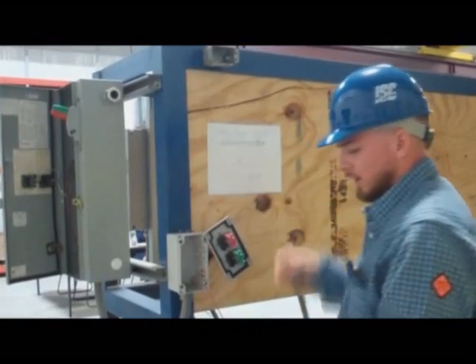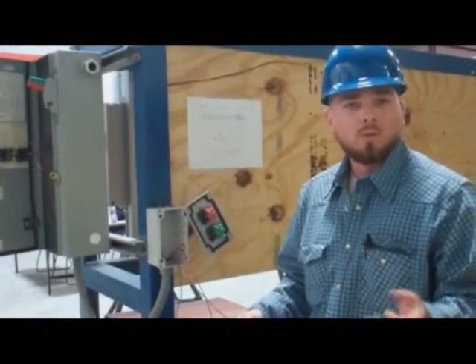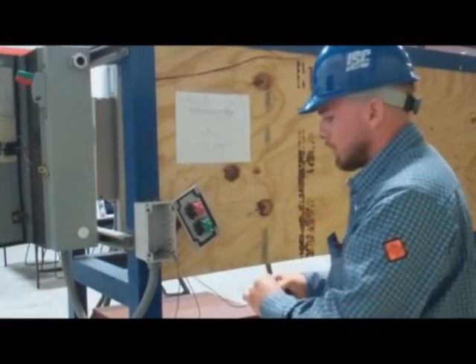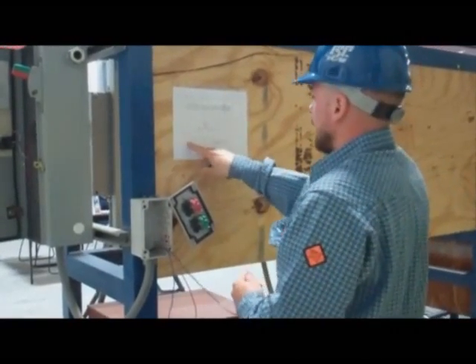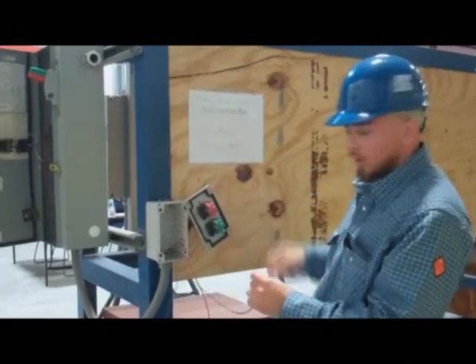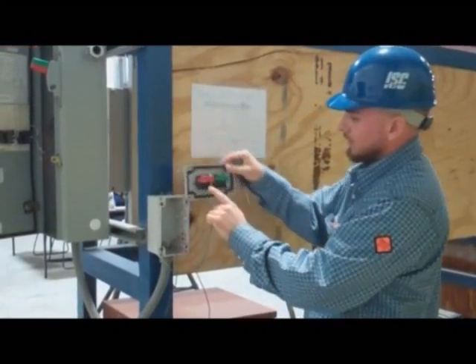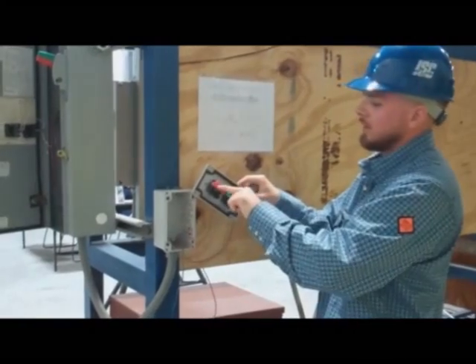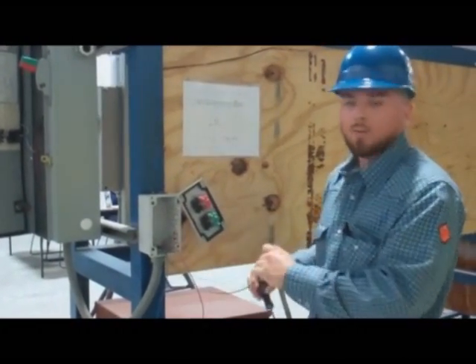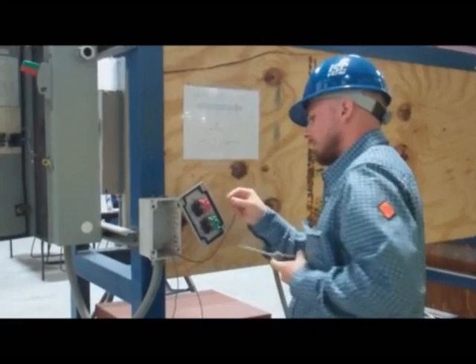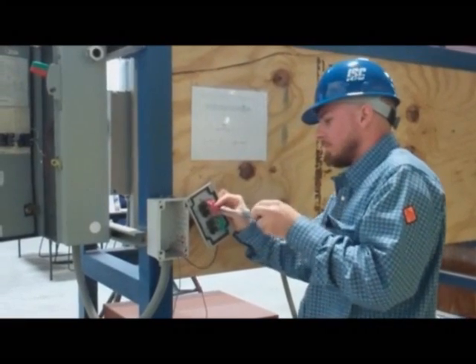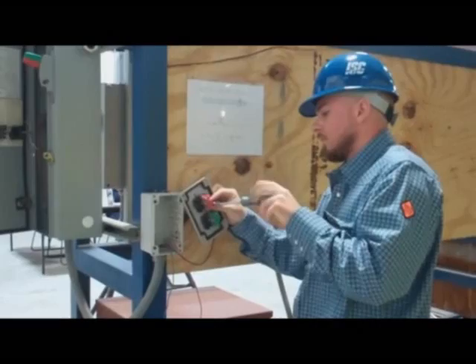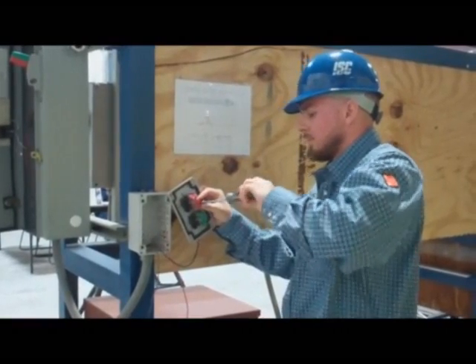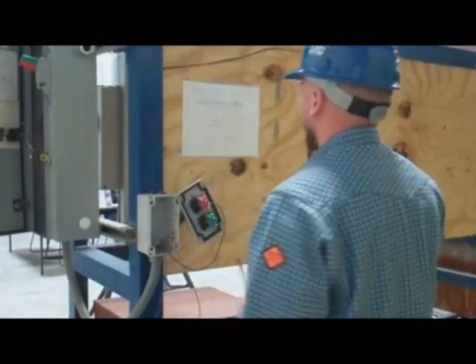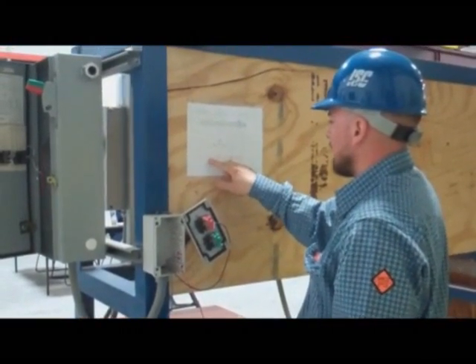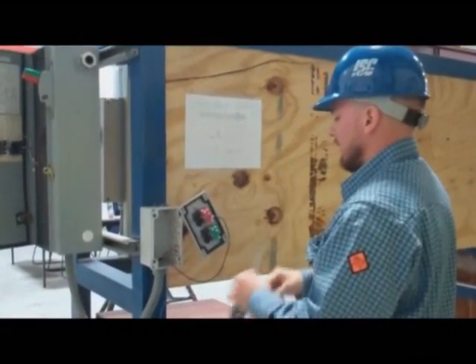So you trace the diagram out. Your black wire will be in one. Most of the electrical, you got black, red, and blue, 1, 2, and 3. It's pretty simple once you get the hang of it. Follow it out, your one goes onto the stop on the normally closed. On all these switches, they got a little number right there that says normally closed, normally open. They're labeled, easy to identify. Then you go through, you find number 2. Goes on your black wire. And your red wire, I'm sorry. On your start.